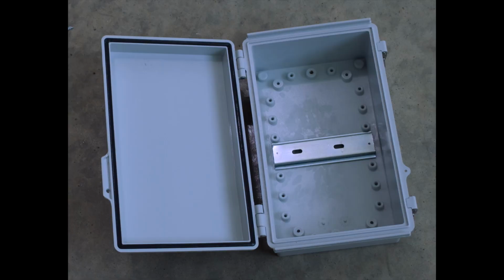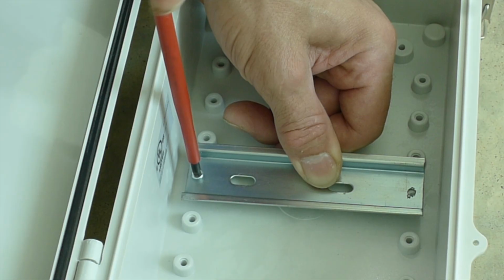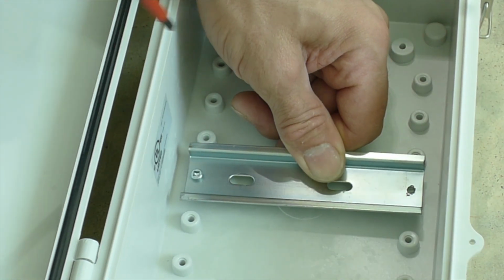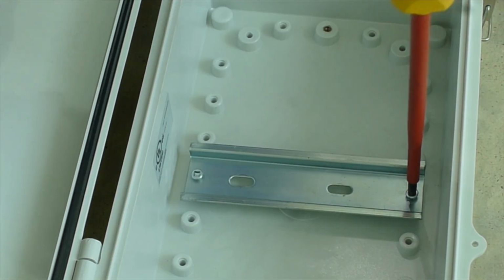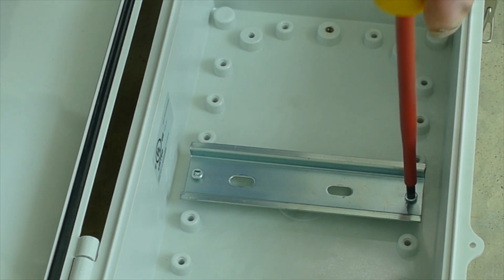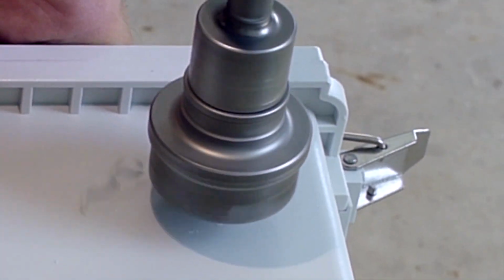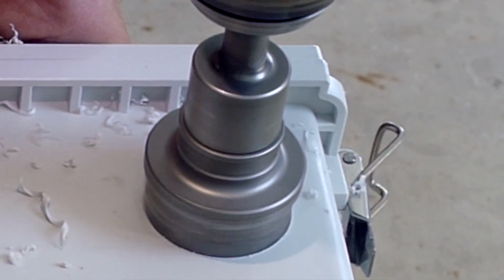Next, I'm using an outdoor electrical box that needs a little modification. This is where we're going to secure the DIN rail and the cable glands. Once we secure it on the wall, we will mount the 125 amp DC circuit breaker.